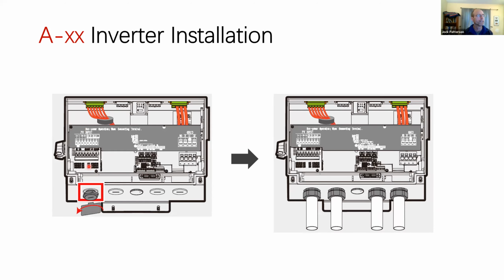Because we're a UL wiring box here, there are plenty of holes for conduit. Any holes you're not using, of course, initially are covered. So when you get this inverter out of the box, it's NEMA 4X rated. And as soon as you take one of these covers off, it no longer is NEMA 4X rated, right? You have to put conduit in with the proper connectors and return it to that NEMA 4X rating. Ideally, you run conduit, say from the roof, coming down and back up. If you come in the side, and there are side openings, one on each side, you always want to be careful about any water intrusion. So you want to use electrical putty or have a drain at the bottom of your elbow, your LB.